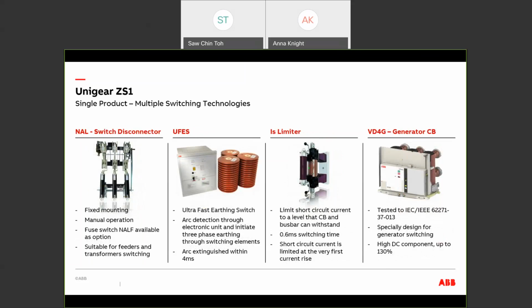We can also mount the switch disconnector, NAL switch, in a UniGear panel. This will be a fixed installation with removable fuse, if applicable. The size of the fuse will depend on the transformer size. For other applications, we have UFS, ultra-fast earthing switch, and IS limiter. We are going to look at UFS later in a slide.